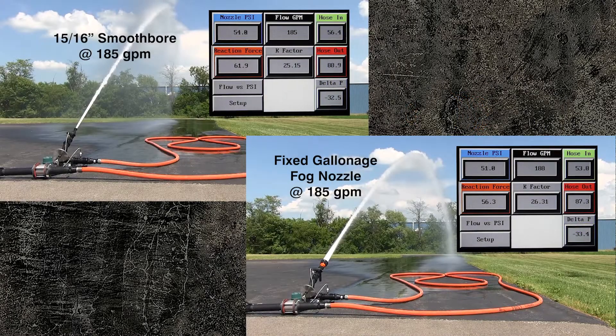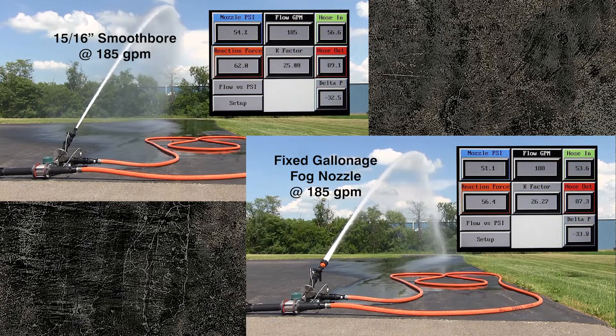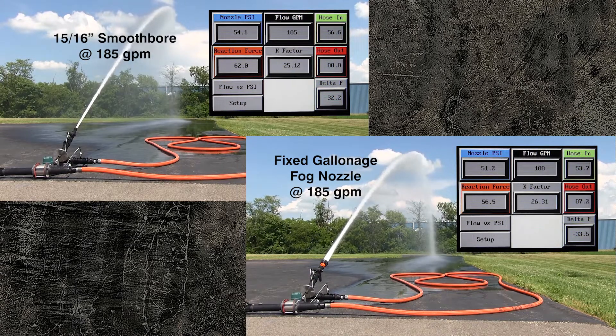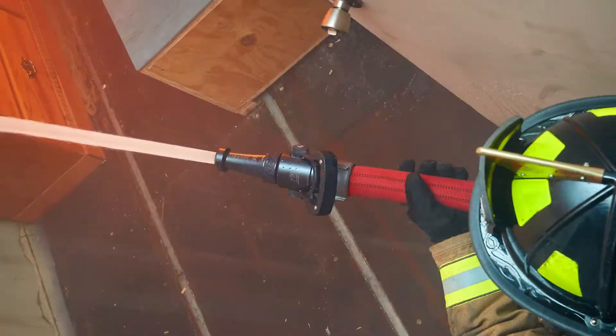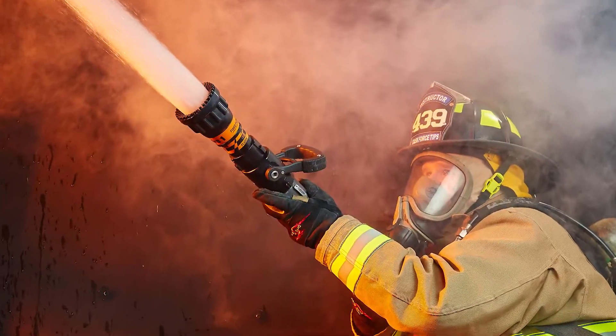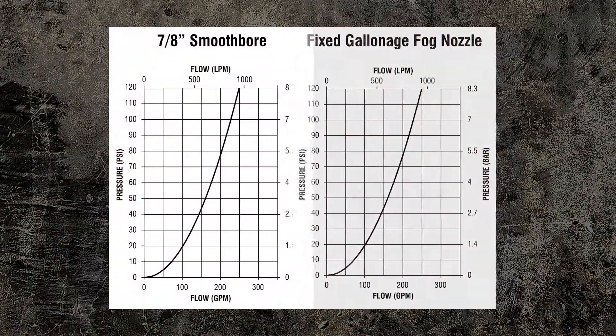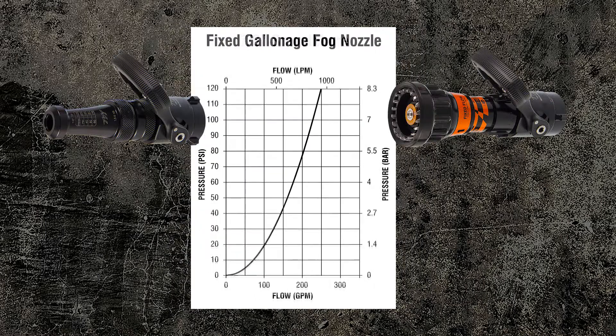If a 15/16 inch smoothbore was selected, we'd get a different flow and pressure curve, and the appropriately matched fixed gallonage nozzle would perform the same. Whether it's a smoothbore or fixed gallonage fog nozzle, you get the same results. The formulas and the field test experiments agree.